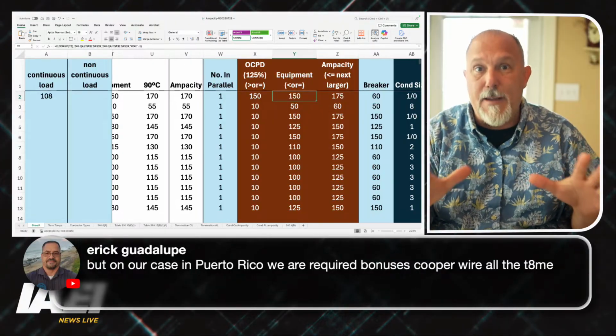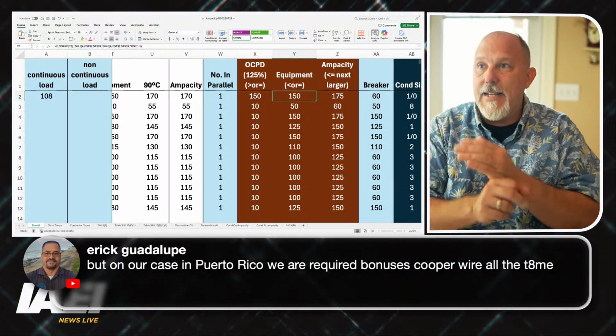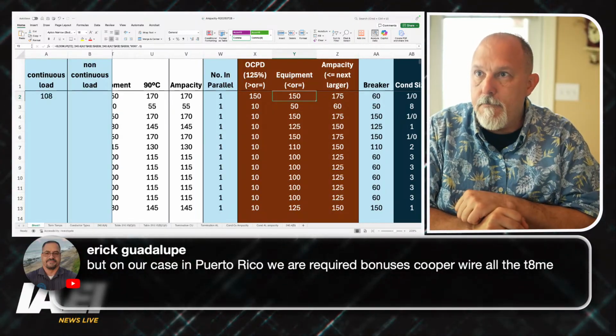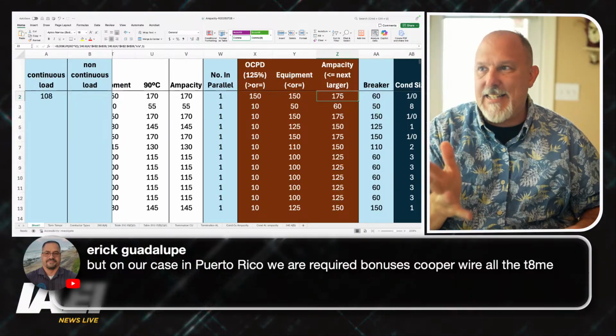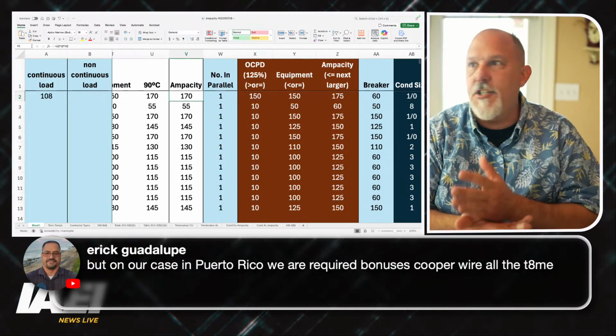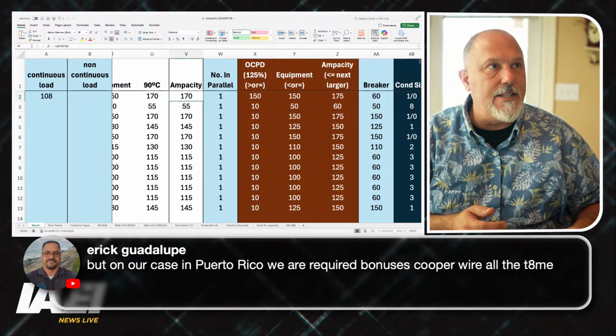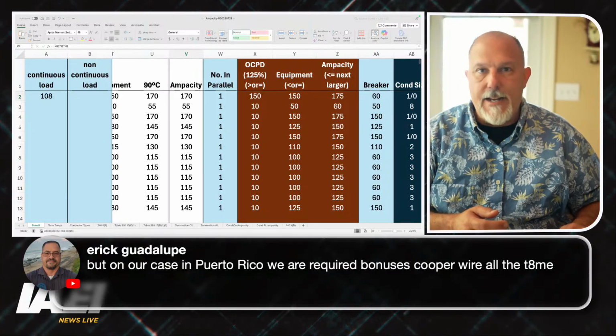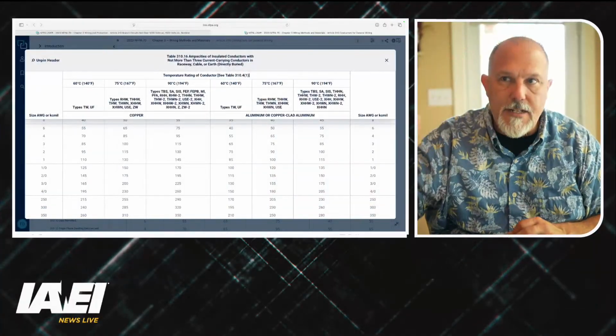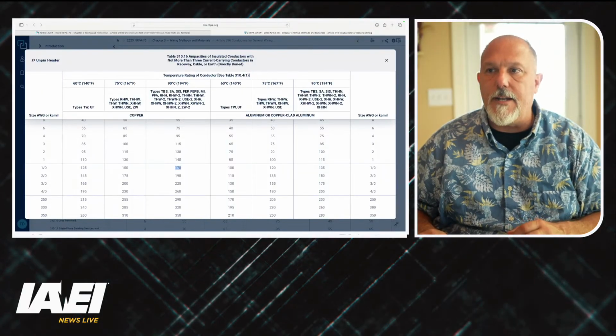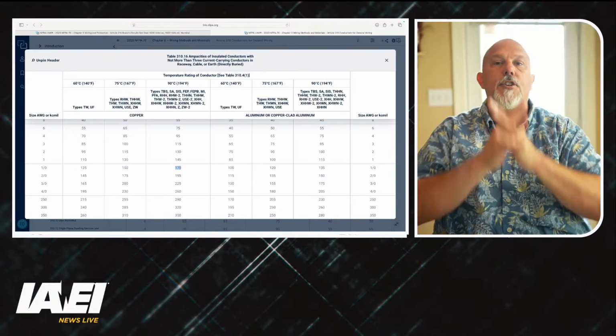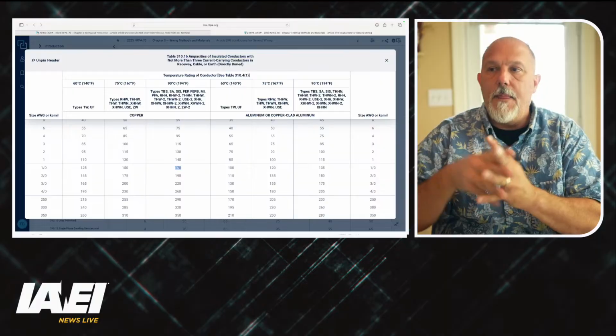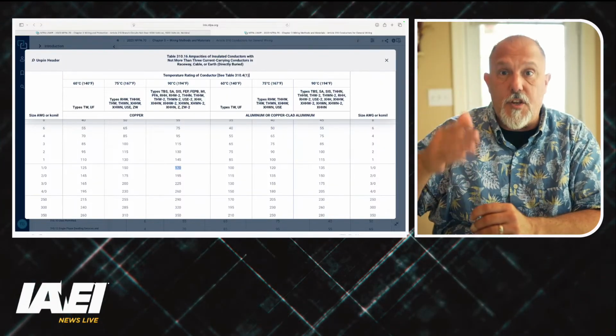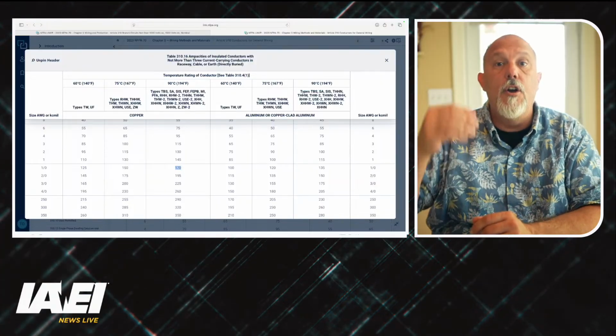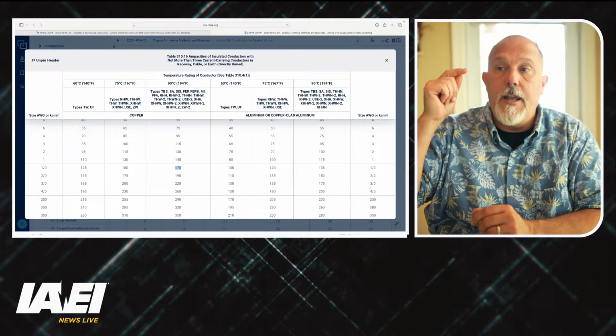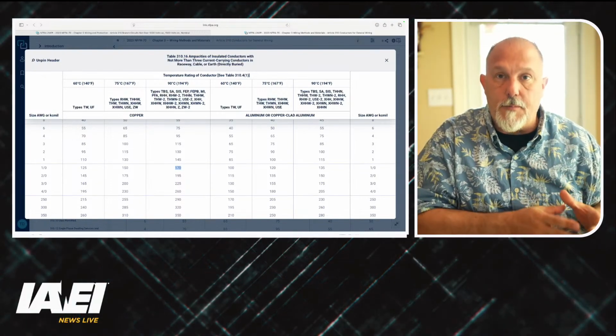My equipment, I have to be less than or equal to 150 amps. So far, a 150 amp breaker is looking really good. I have to be less than or equal to a 150 amp circuit breaker. And my ampacity is 170 amps based upon conditions of use for this 90 degree C 1-aught conductor. If I look at the 90 degree C column on Table 310.16, I'm going to see that my 1-aught conductor is 170 amps. So my ampacity is 170. The next larger overcurrent device, because I'm permitted to go to the next larger overcurrent protective device above the ampacity of the conductor, is 175 amps, which is a standard overcurrent protective device size.